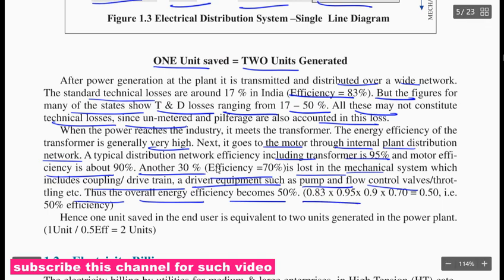Overall efficiency becomes 50%. That is 0.83 × 0.95 × 0.9 × 0.70. That is 50%. It means 1 unit saved at the end user is equivalent to 2 units of generation in the power plant.